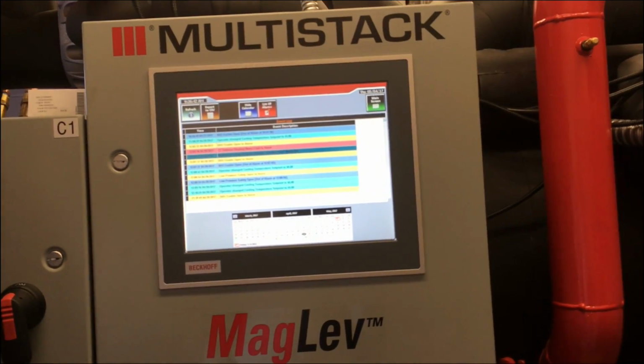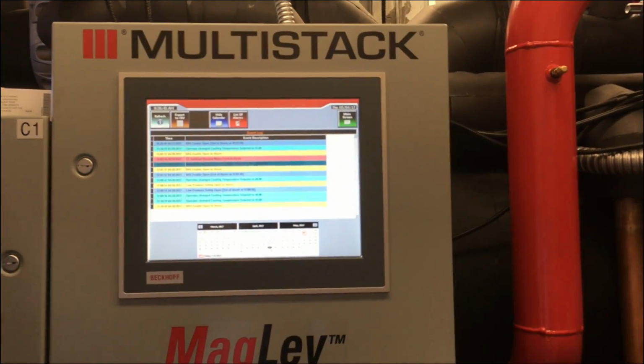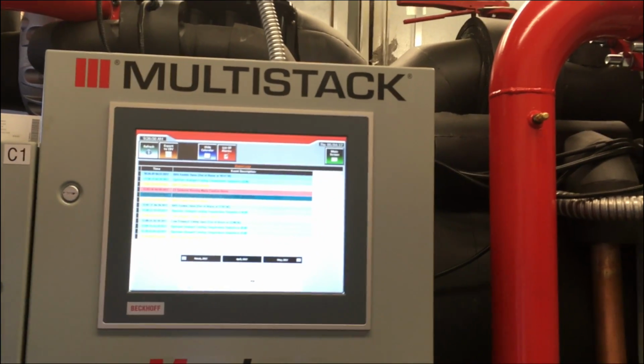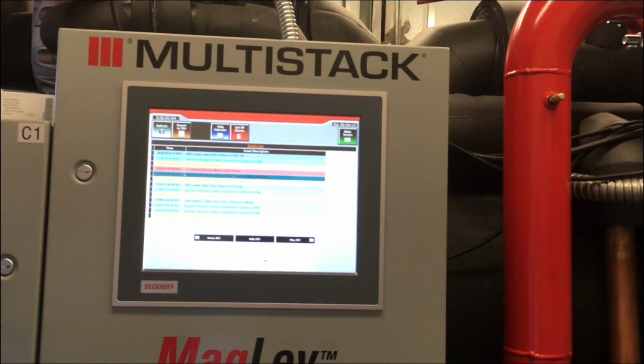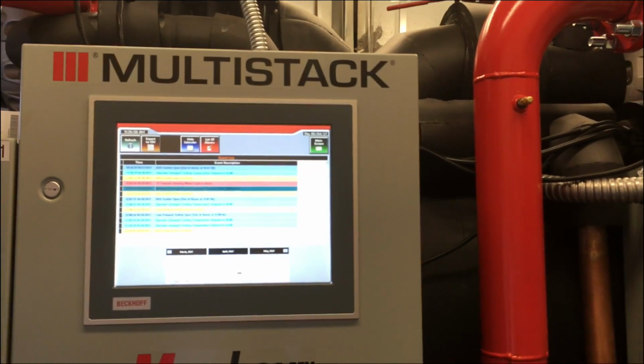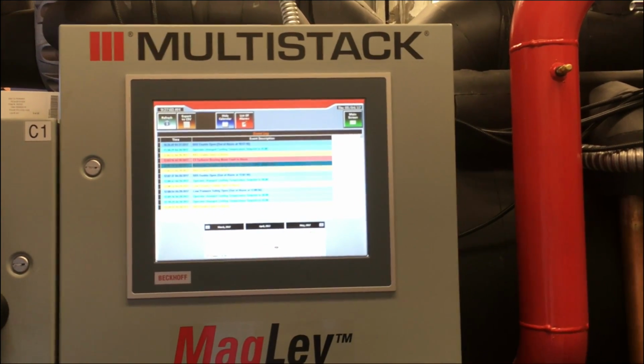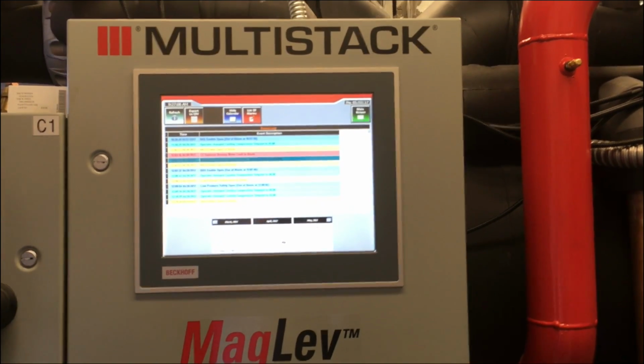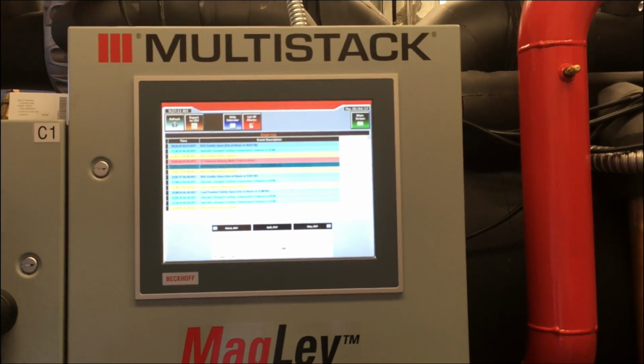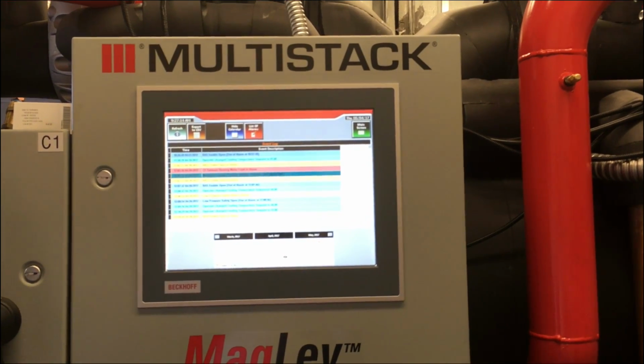So the control guy tried to explain it, but I'm not the control person. It's too technical, but he is saying that it clears out the previous set point and it goes to default. And the default was 0, which is no good. But here it stays 45. And he said that whatever is on the computer, if the power is recycled, the machine will run on its own set point. This stays at last state. So if we lose power there, whatever the last signal to this was, it will stay. So you should be fine.